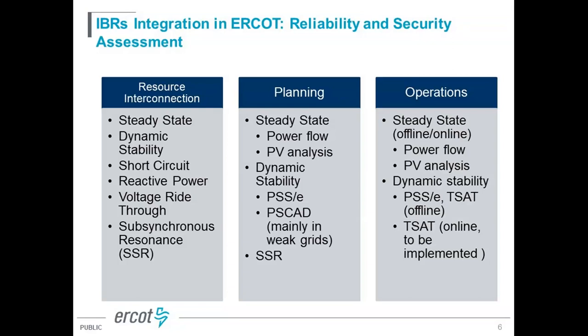Moving to operations, the offline tools are still very typical: steady state and voltage stability analysis. For the online tools, in ERCOT we have a real-time voltage stability assessment, running every 10 minutes, which is more like a steady-state voltage stability analysis. With increasing inverter-based resources connected to the system, the dynamic stability challenges associated with the installations need to be addressed. To better identify and manage the stability constraints in real time, we are currently considering, and have under development, the implementation of real-time transient stability assessment tools as well.